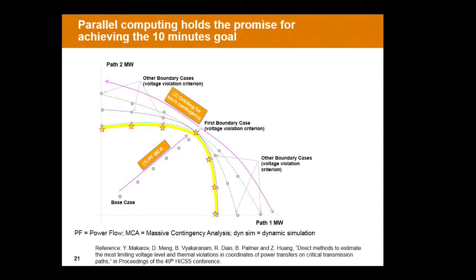This is the end of the steady-state-based approach. Next, we want to identify if these points can survive transient stability by running dynamic simulations. Each star here will trigger different types of dynamic simulations under different contingencies. If something is wrong, we have to scale back the flow a little to make sure transient stability is satisfied.